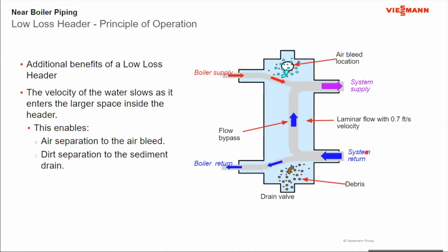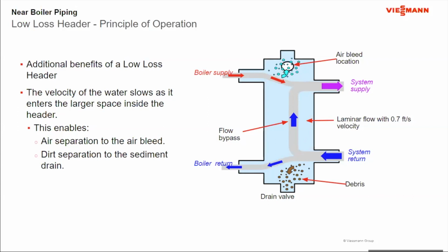If there's any dirt or debris in the system, the velocity of the water tends to move that dirt along until it hits a point of low velocity. Again, inside the low loss header is a point of low velocity. So you do end up with a fairly effective dirt trap on the bottom as well. So although it's there for hydraulic separation, there's a couple of features that are also picked up as auxiliary or ancillary features in the low loss header as well.